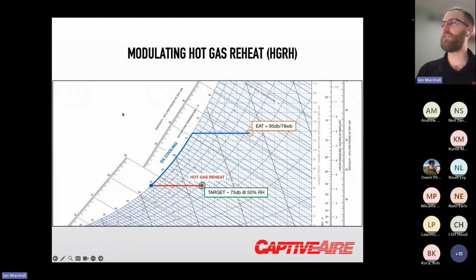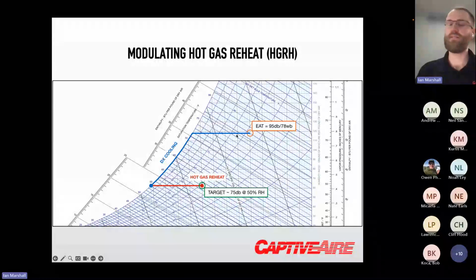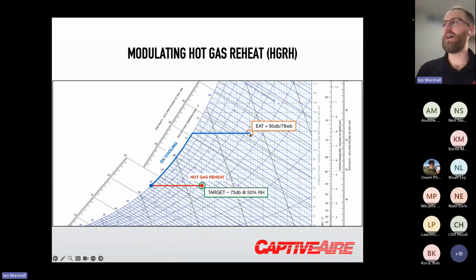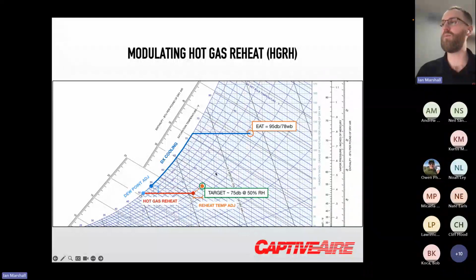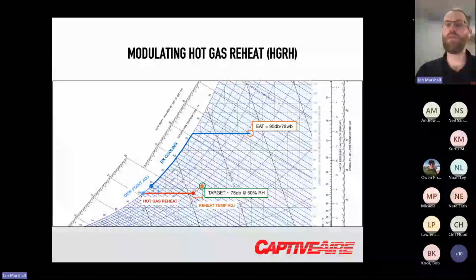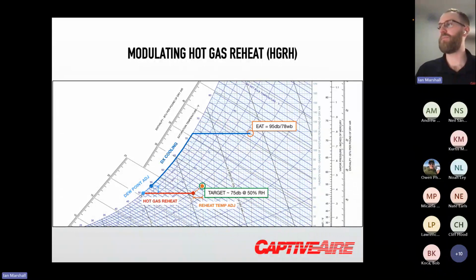Our hot gas reheat logic, or hot gas reheat in general, is shown here on a psychrometric chart. It takes that hot, humid outdoor air and cools it down to saturation, and that's when you start pulling out moisture. You drop down to, say, 55 degrees, fully saturated. You utilize the hot gas reheat to reheat that air up to a more neutral temperature. We utilize a reheat dew point adjustment to overshoot a dew point setpoint when we're doing space control. So we're never prioritizing a call for cooling over dehumidification, or vice versa. That is one of the benefits of the logic that we have.